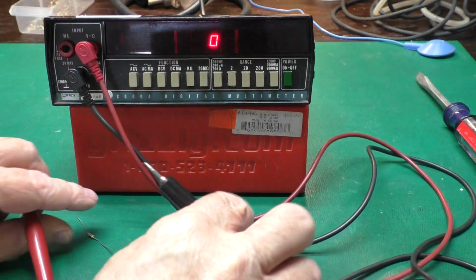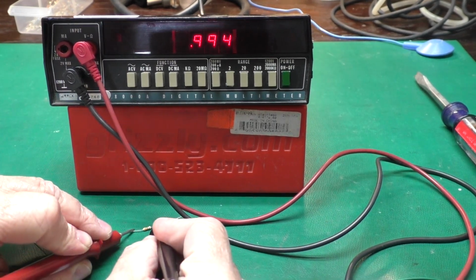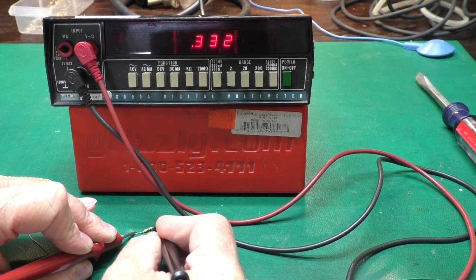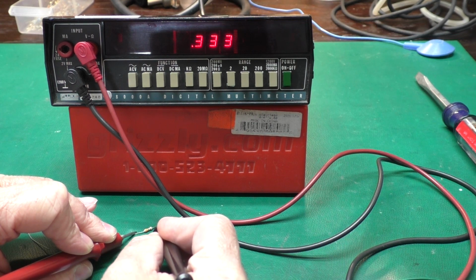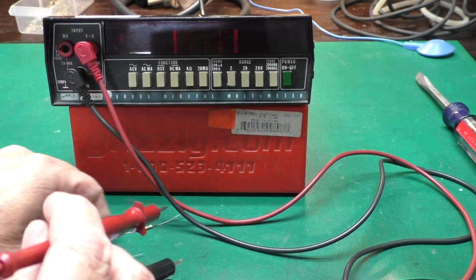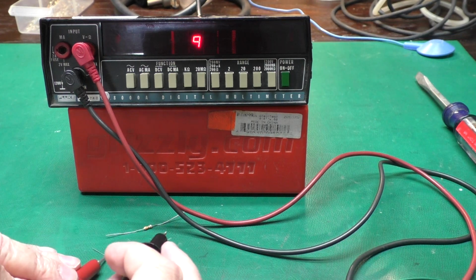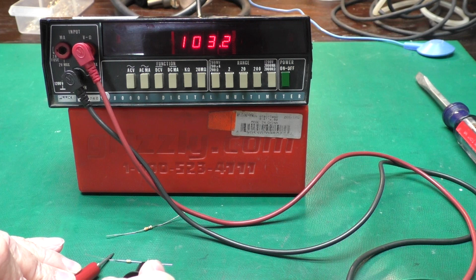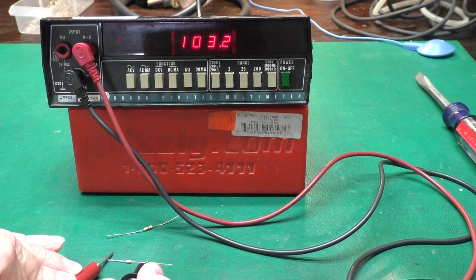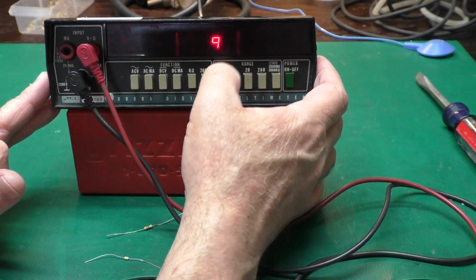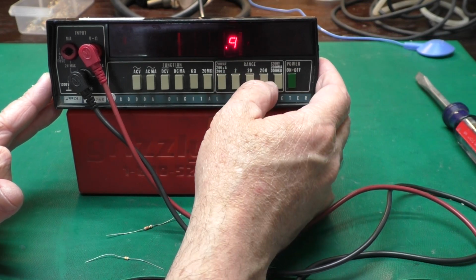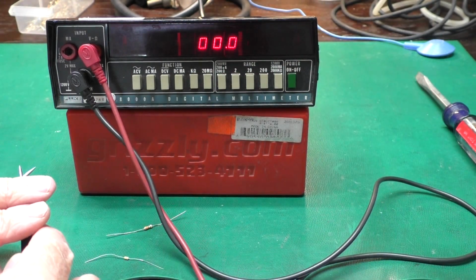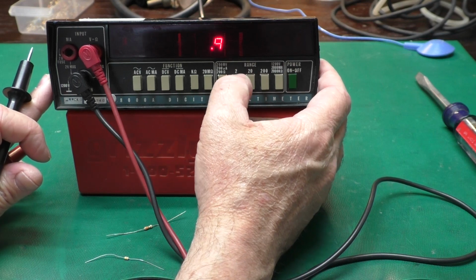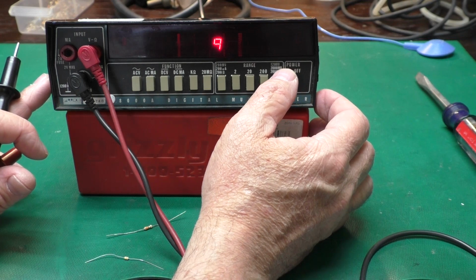So 2K, if we measure the 330 ohm, yeah, on the HP it was measuring 330, 331. So this is reasonable for a 3.5 digit. And then for the 100K, to put it in 200K range, 103, and it was measuring over 100 on the HP as well, so that's reasonable. Now let's try the... I'm not sure what that... That seems odd that that number sticks there like that. I'll read the manual and see what that does, and we can also check the other one and see if it does the same thing. Yeah, we'll try some DC volts next.